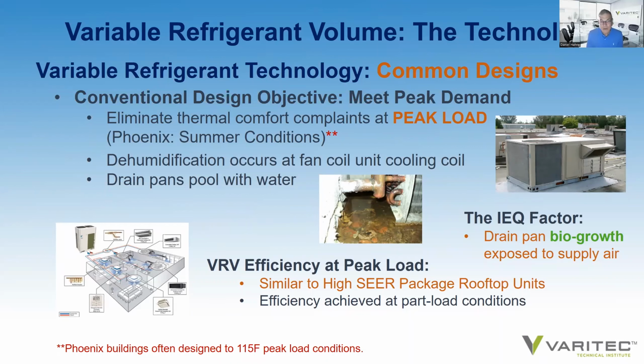Consequently, you have drain pans that begin to fill with water, and you have to have, in some applications, even condensate pumps necessary to drive that water out of the building so that it's not hanging in the pans and overflowing in certain design applications. If you have water in drain pans, however, there is a biogrowth concern that could impact building IEQ, and it will also add to some of the humidity load within your building.